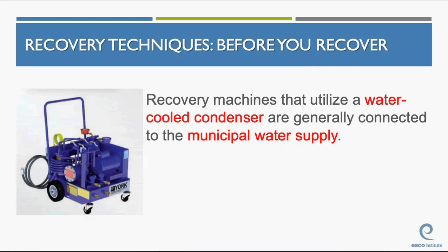There are recovery machines out there that use a water-cooled condenser. Okay, these are for majorly large systems, not something you're going to carry in your truck. If you ever have a recovery machine that uses a water-cooled condenser, they're generally connected to the municipal water supply. In other words, whatever the building water supply is, okay? Water-cooled condenser. They're connected to the municipal water supply, okay? They don't recycle water. They basically use it and dump it.